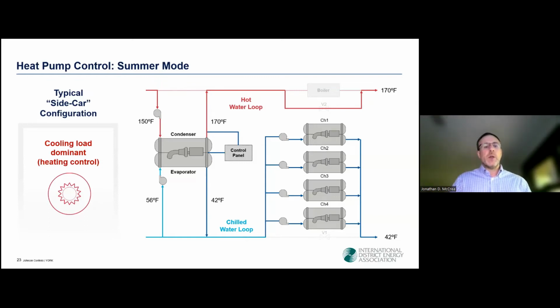So the boilers are off and the heat pump is handling all of the heating needs in the system this time. And over on the chilled water side, our heat pump has plenty of heat source with the relatively high summertime chilled water load. And its dedicated pump is flowing a portion of the 56-degree return through the heat pump's evaporator. It's delivering around 42 degrees chilled water. That's then mixing with the rest of the return chilled water and then flows down to the main bank of chillers, where it's brought to 42 degrees, which is what we need in supply temp for the rest of the system. So in essence, we're extracting heat from the return chilled water.